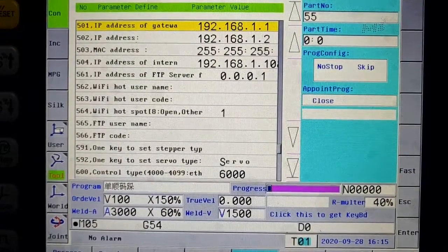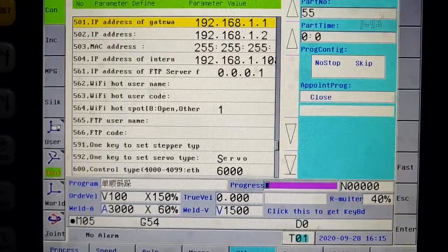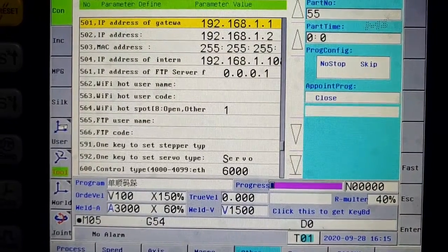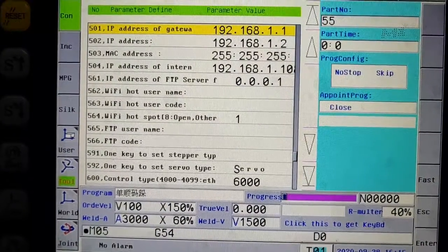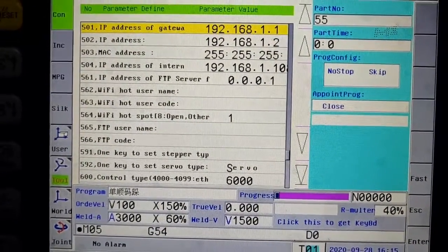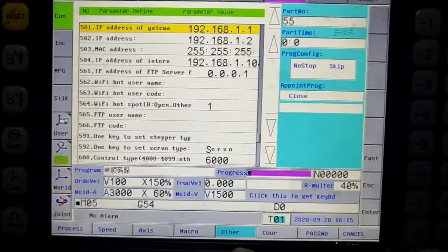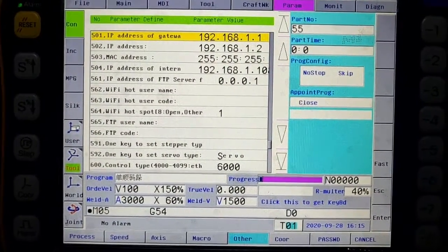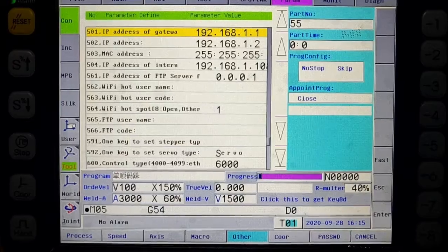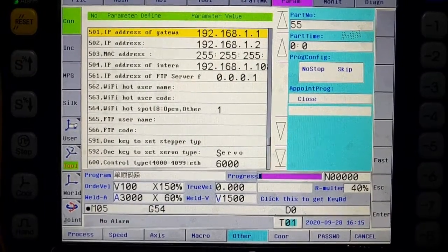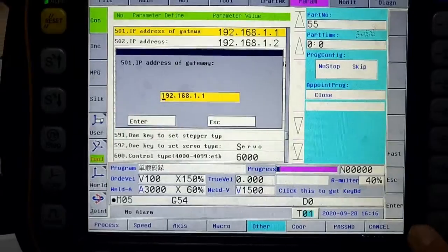Parameter 502 is the address of this controller. Normally we set it as 2 if only connected with computer, and its first 3 bytes is the same as the value in computer IP address settings.